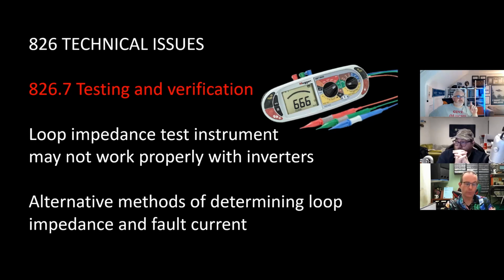John, also one of the issues that we found a lot on industrial, when you're measuring the fault current levels for the protection device to disconnect, you need to have sufficient fault current levels. When you go into battery systems, unless you have an inverter that's able to deliver said fault current levels, you may not get the protective device tripping. It's one of the biggest issues on UPSs, where the inverters are too small because they run, say, emergency lighting, but it's connected to a board, and you have, say, a C10 amp breaker, you need 100 amps to trip, but the inverter can't deliver 100 amps, so you're never going to get your breaker to trip anyway. So there's lots of things in consideration we need to think about when we're working around this technology, including not blowing anything up.